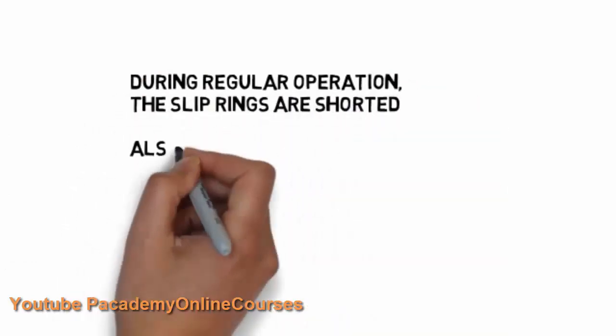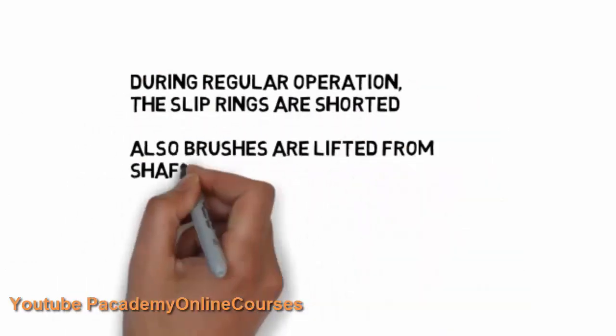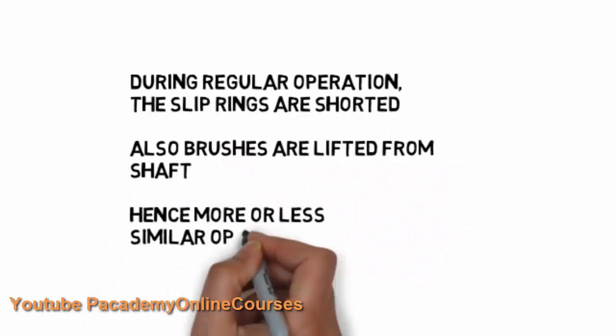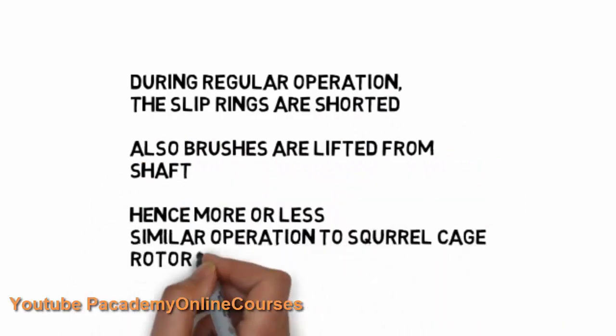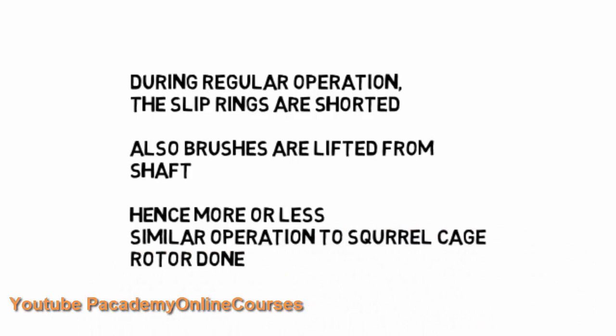During regular operation, the slip rings are shorted and brushes are lifted from the shaft. When shorted, it will act like a squirrel cage with shorted end rings, and more or less similar operation to squirrel cage rotor is possible during running of the motor.